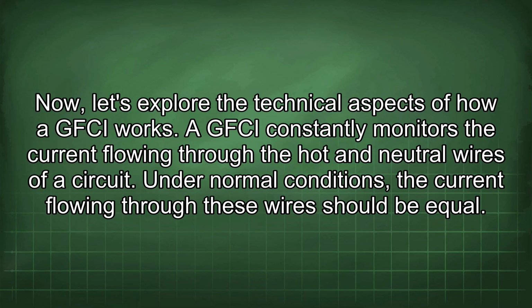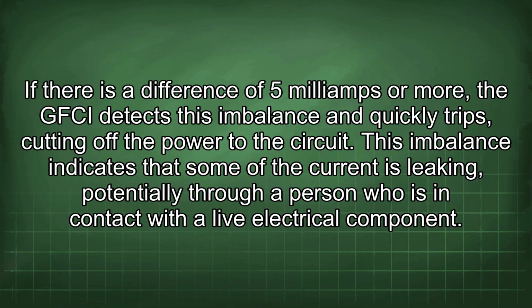Now, let's explore the technical aspects of how a GFCI works. A GFCI constantly monitors the current flowing through the hot and neutral wires of a circuit. Under normal conditions, the current flowing through these wires should be equal. If there is a difference of 5 mA or more, the GFCI detects this imbalance and quickly trips, cutting off the power to the circuit.